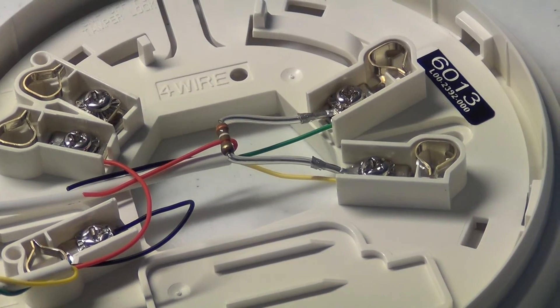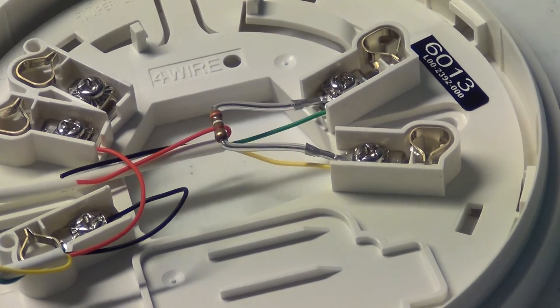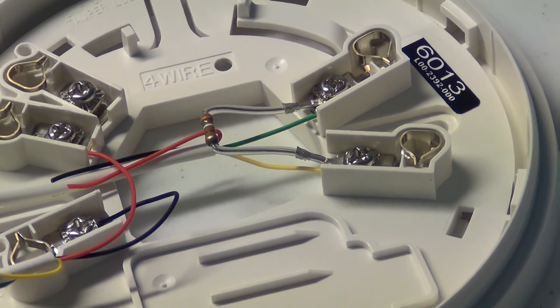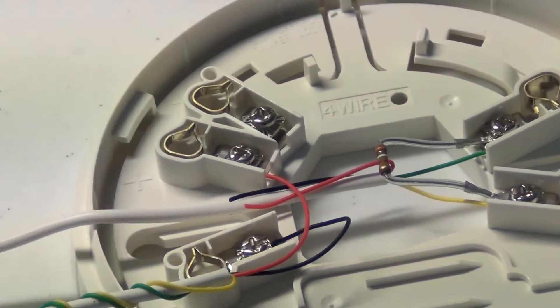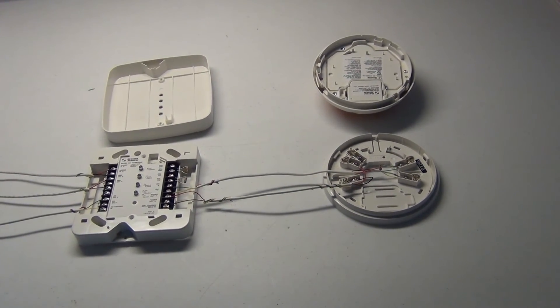At the very last one in the line you're going to use this resistor they provide with the module and you'll run it in parallel between the two terminals. You can only fit 12 smoke CO combos per one module.